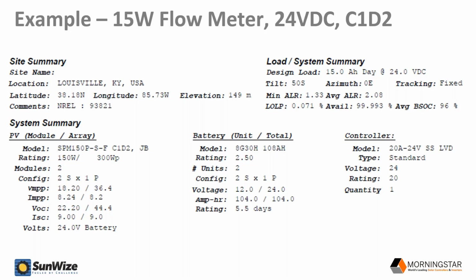The other thing I want to point out is that note that the design load we list in amp hours per day, that's very convenient for a number of reasons. It lets us combine loads at different voltages and get one unified number. It also allows us to do back of the envelope calculations around autonomy really quickly and easily. So if we know we have a 100 amp hour battery bank and a 20 amp hour load, we can know in our head that we've got a 5-day backup design for that system.